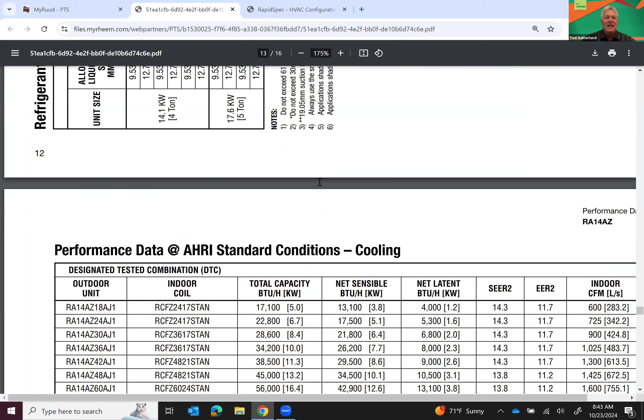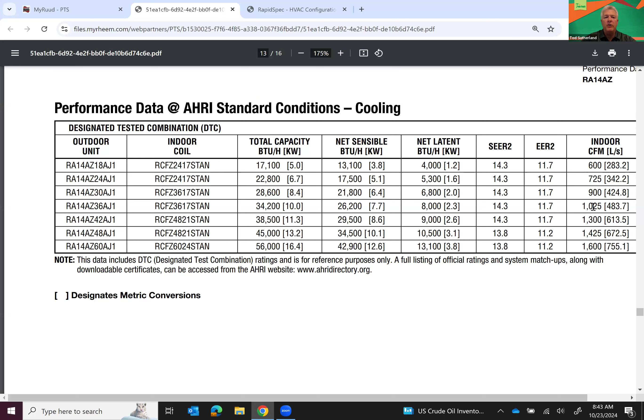Okay. When you're looking at the RA14AZ36, does it list it with the air handlers? Let me see if it does. No. All right, but this is going to give us the same information. Okay. You'll notice that we're at 34,200 capacity, and we're at 1,025 CFM. So this is what the designated test combination is. All right, so that is what it's rated at, at AHRI conditions at 0.5 static pressure. So we have 1,025 CFM, not 1,200 CFM on that 3-ton.